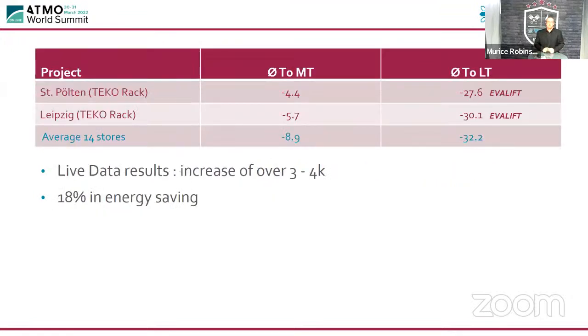So having a look at the average of the 14 stores, we had an average suction temperature of -8.9 on the medium temperature. And on the low temperature, we had an average temperature of -32.2. The 2 stores that we had with EVALIFT, you can see that our MTs were running at -5.7 and -4.4, and our LTs were running at -30 and -27.6. So you can see there was quite a big difference over there. The live data results had an increase of over 3 to 4K, and that resulted in 18% energy saving. Just to emphasize how much energy we saved over an average of 14 stores.